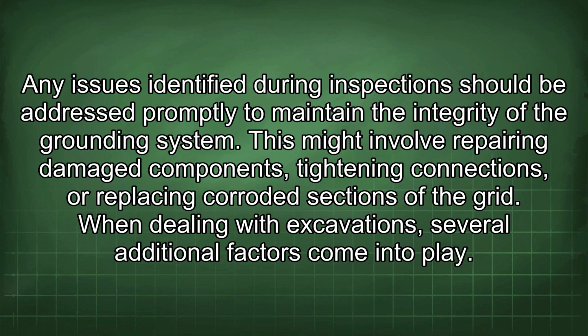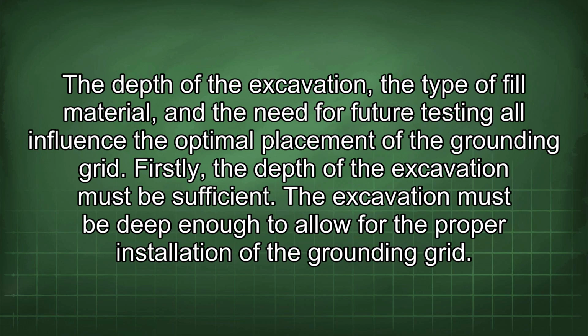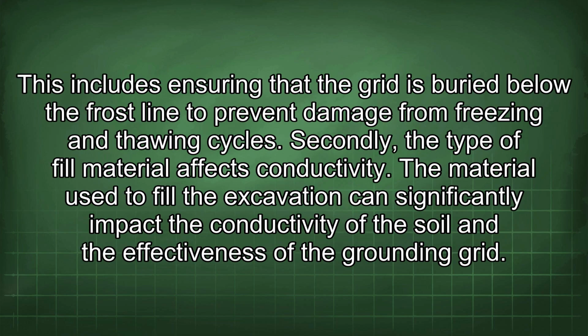When dealing with excavations, several additional factors come into play. The depth of the excavation, the type of fill material, and the need for future testing all influence the optimal placement of the grounding grid. Firstly, the depth of the excavation must be sufficient. The excavation must be deep enough to allow for the proper installation of the grounding grid. This includes ensuring that the grid is buried below the frost line to prevent damage from freezing and thawing cycles.